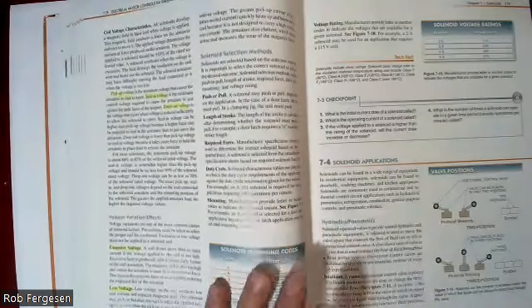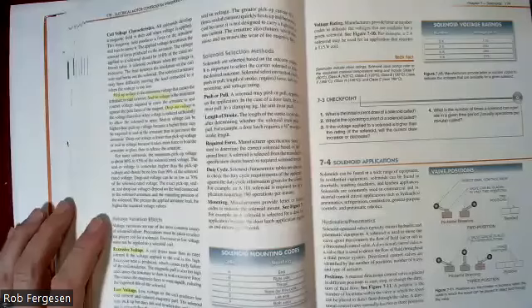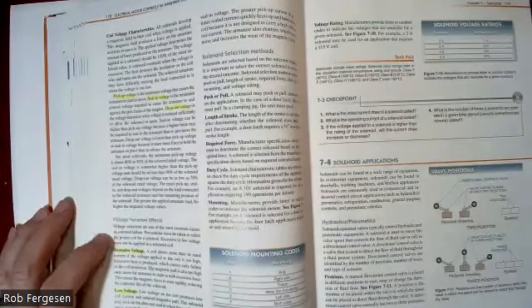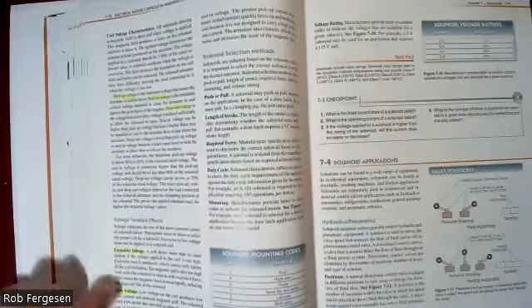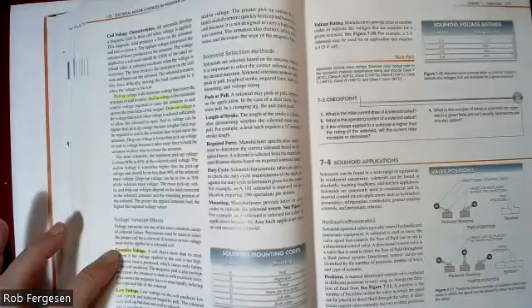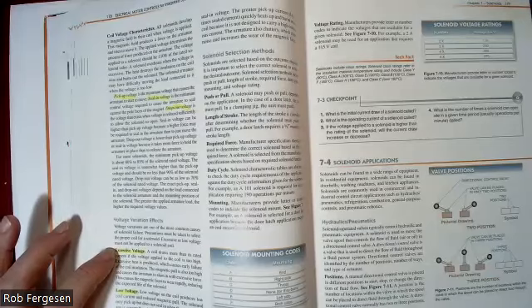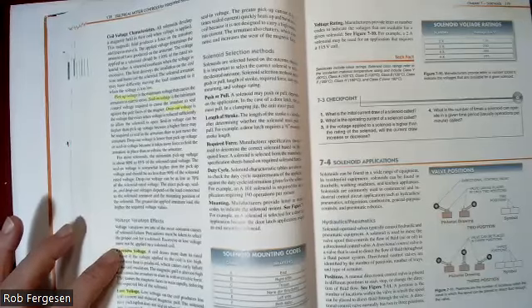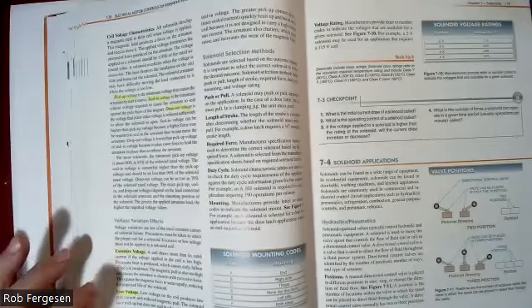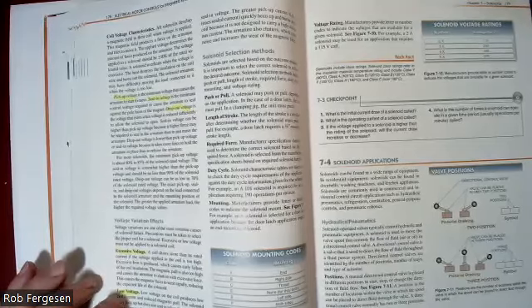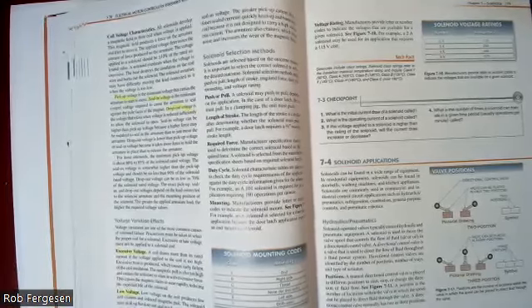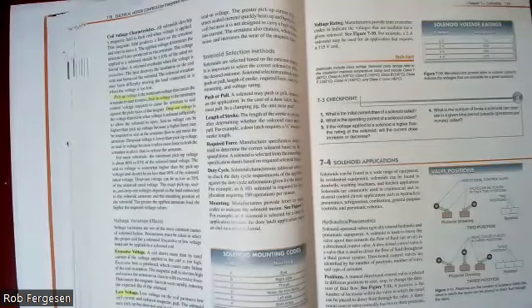Various problems you can have with the solenoids are excessive voltage and low voltage. Excessive voltage can cause a variety of problems. A lot of heat added when you put too much voltage in there, early failure. Low voltage actually creates high current, which could also create failure. These are pretty classic problems with any kind of solenoid.